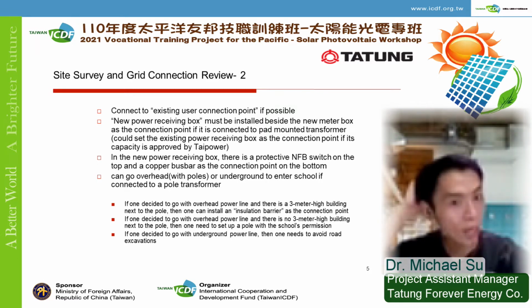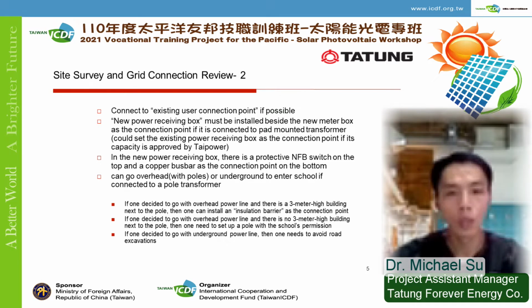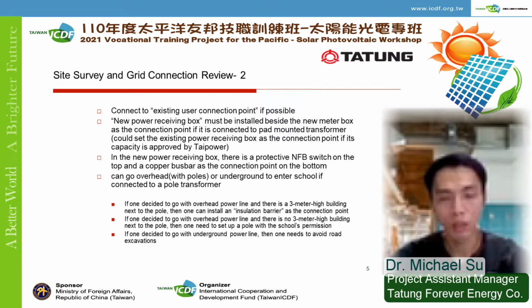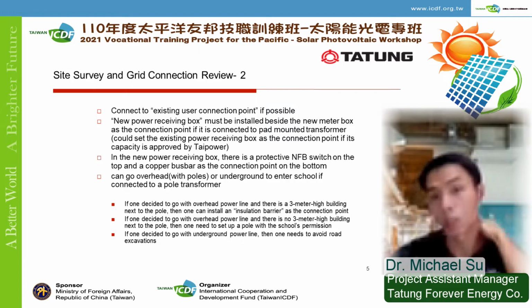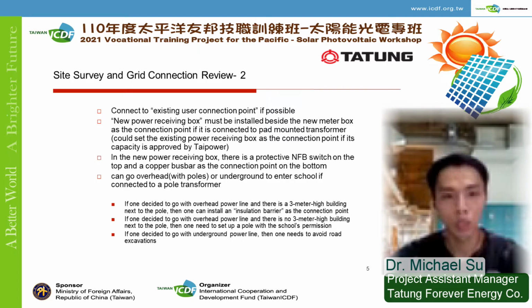What are the user's connection points? If you open it up, you'll see the wires coming from the user connecting to TPC's cables directly with tapes. If we want to connect to the transformer on poles, since the cables can't be connected directly to TPC's transformers, we need to put on a new distribution box with guarded switch inside next to the transformer for the connection and also to be used as demarcation point.